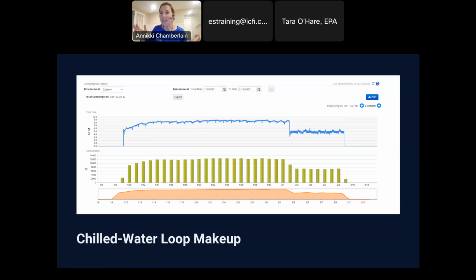And I was like, oh my gosh. So we're thinking there's a leak. They're running around trying to find it. But as I say, always have a routine if you have a leak, because the first thing you should do is just walk the line, whatever the line is. So after looking for it for an extended period of time and trying to contact leak detection agencies, because we were thinking it was underground, the engineer walked the line and found a valve that had been left open, a manual valve that had just been left open in some dark corner for some bizarre reason.